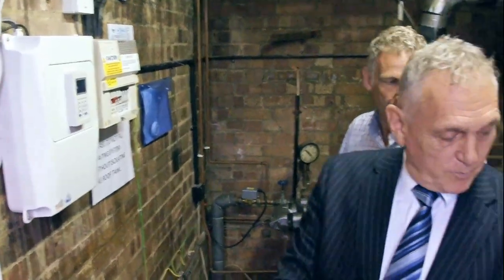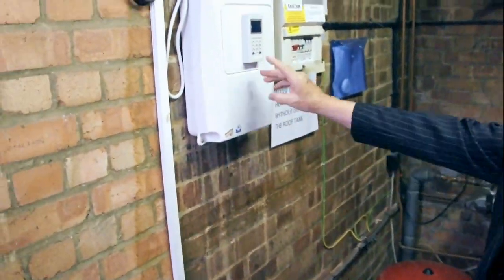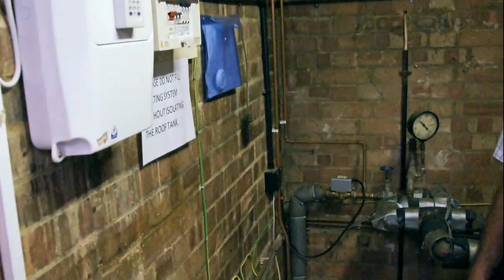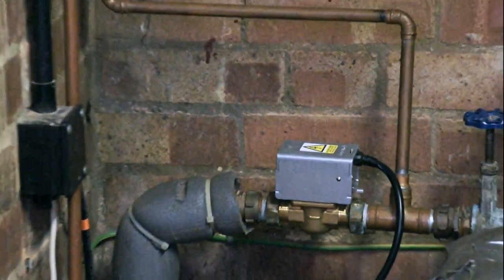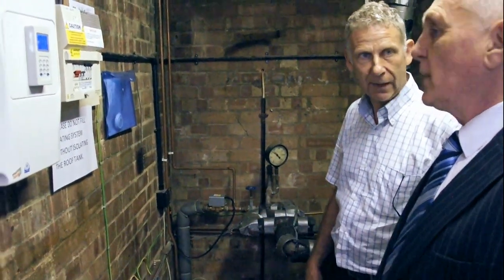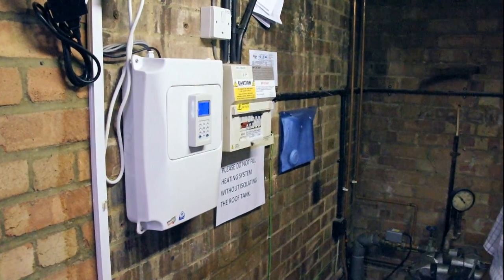So in here we've got the plant room, and we've got a boiler right behind me. This is the 3520, which is the HeatingSafe controller. You push the button there — that's all working. That wired connection is controlling the zone valve over there — a Honeywell zone valve — plus also a circulating pump on that system. So when we call for the hall, which has got multiple radiators, it opens that valve and turns on the pump. That's done directly from the 3520 controller. But the 3520 controller is also the heart of the ZigBee network — that little area on the side there — talking to the other range extenders to get to all the radiator valves. They're all part of that network.